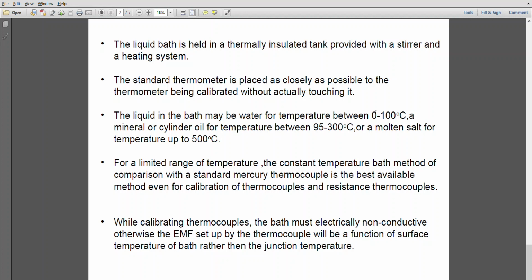The liquid bath is held in a thermally insulated tank provided with a a stirrer and a heating system. The standard thermometer is placed as close as possible to the thermocouple being calibrated without actually touching it, so that both the hot junction and the thermometer bulb are very close to each other.